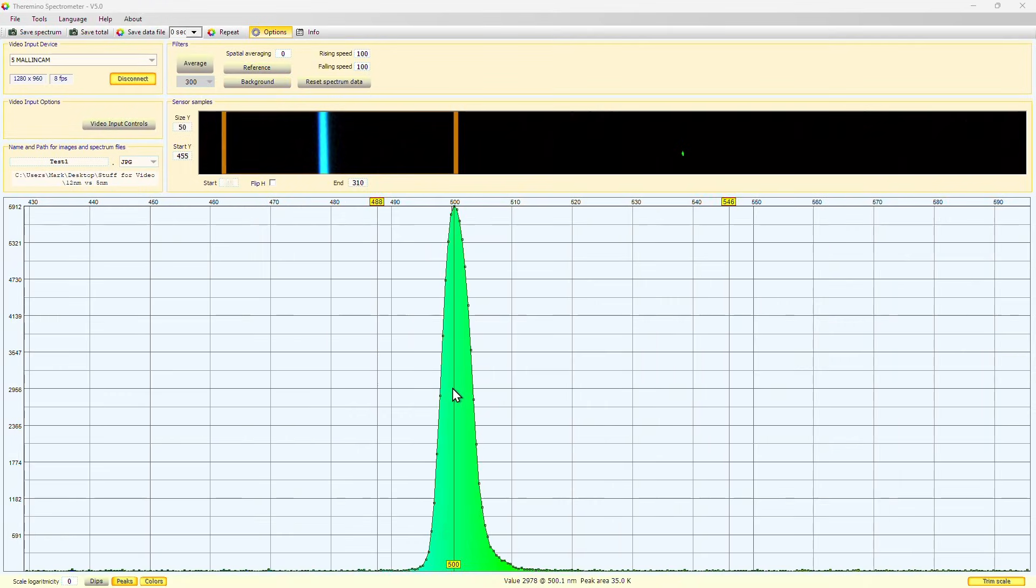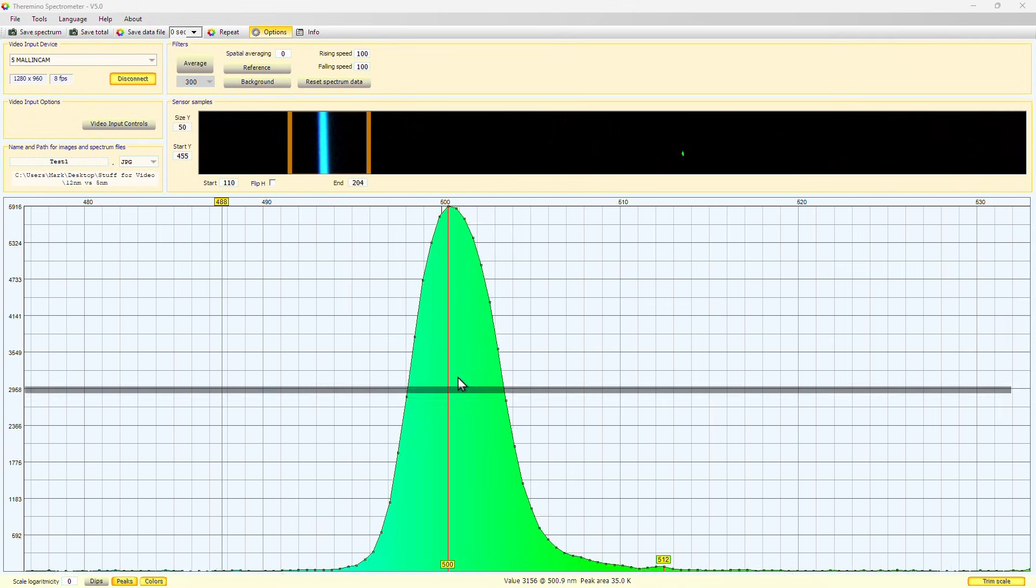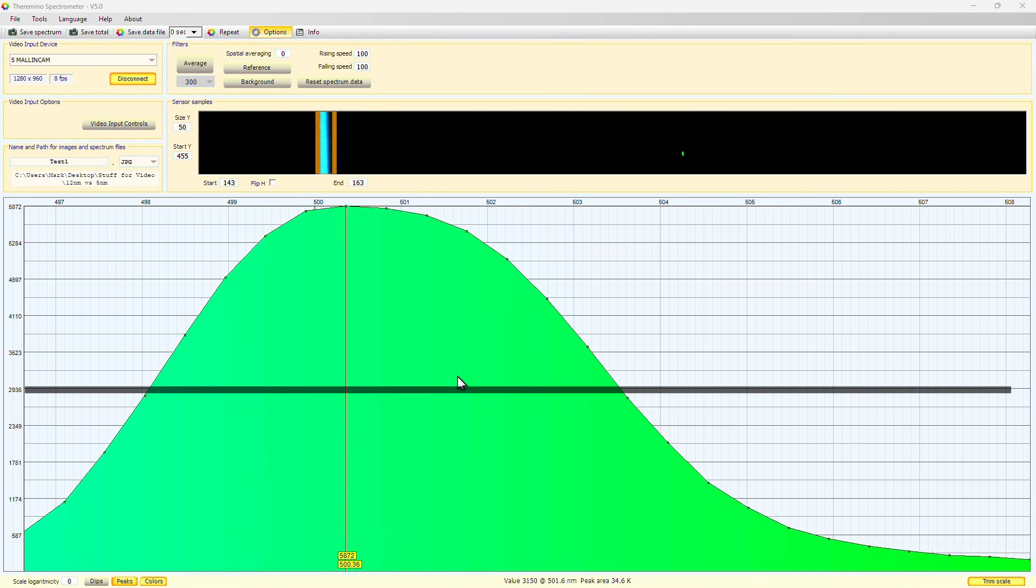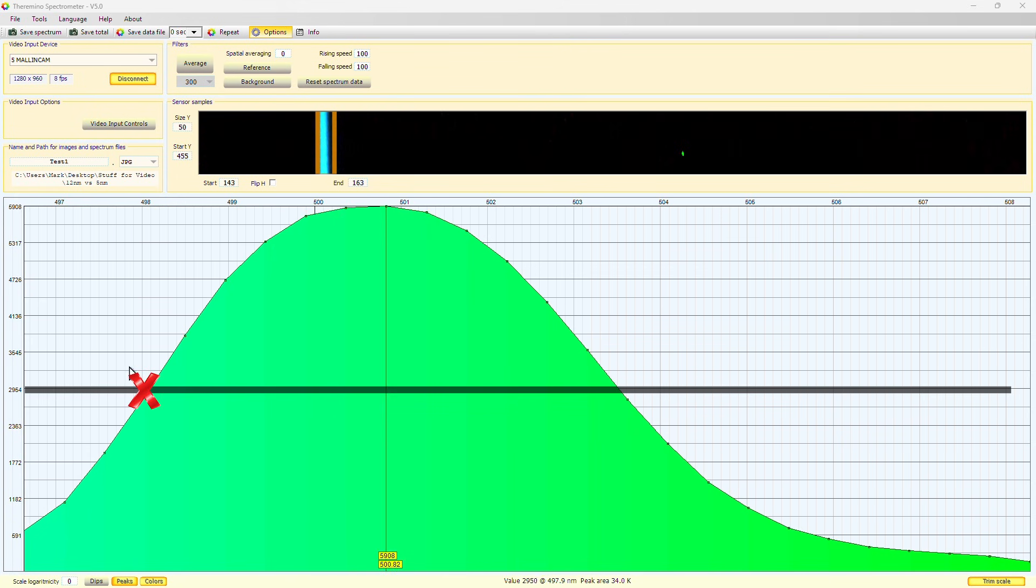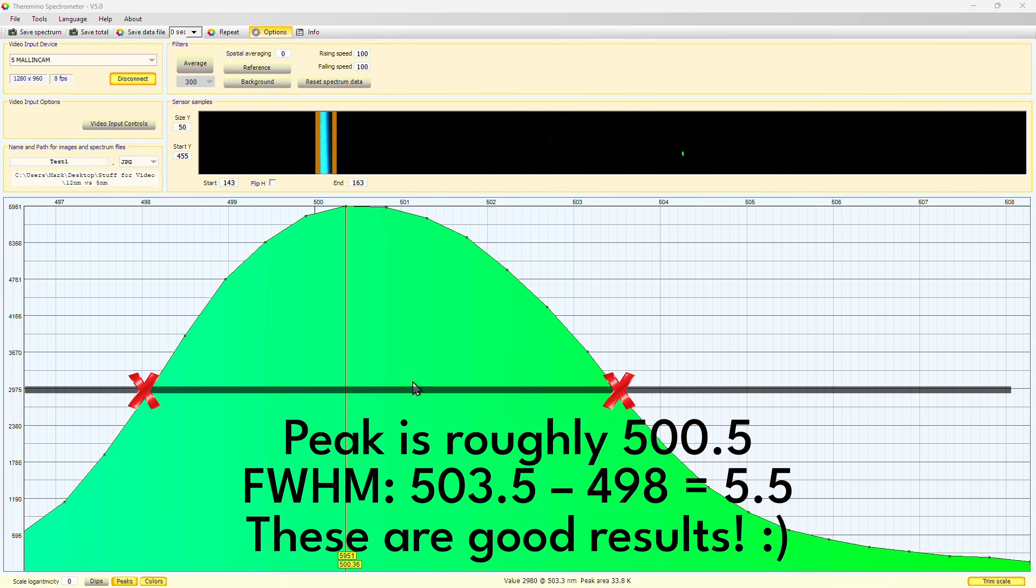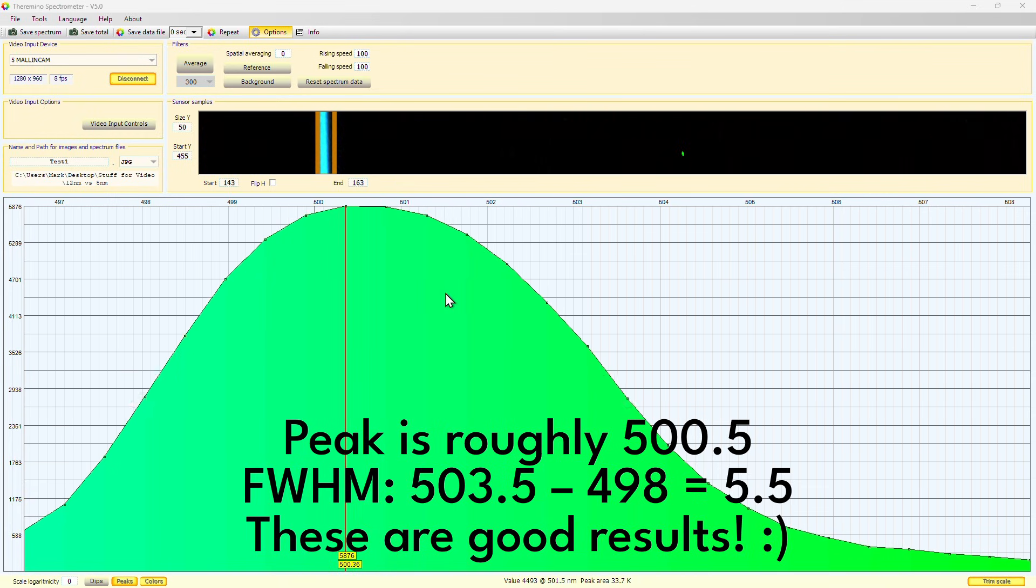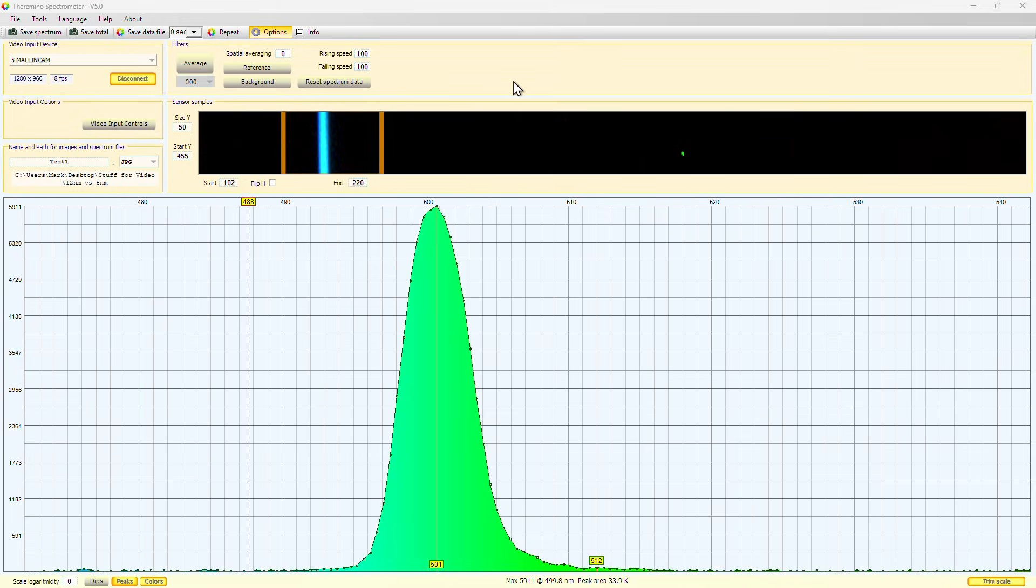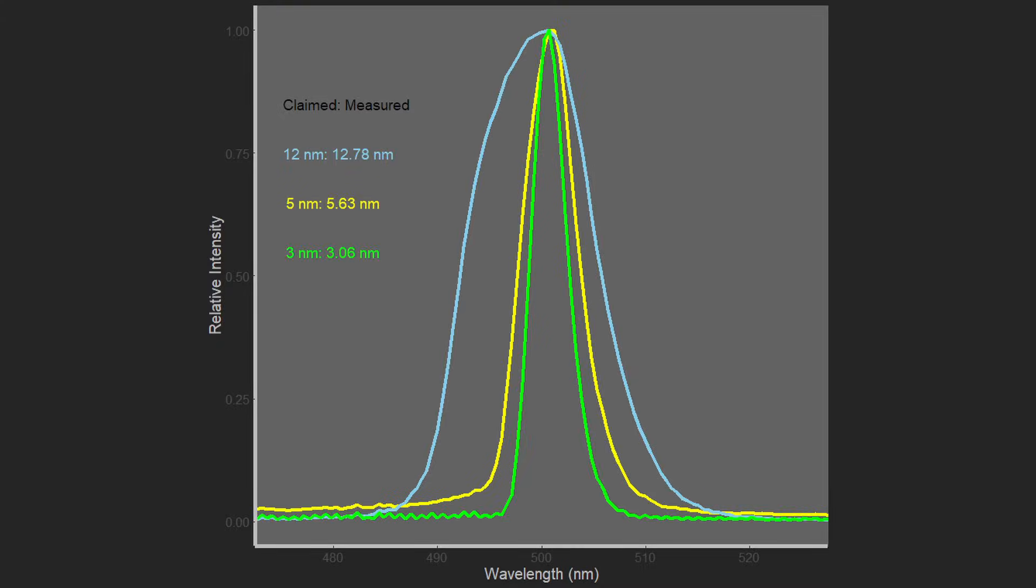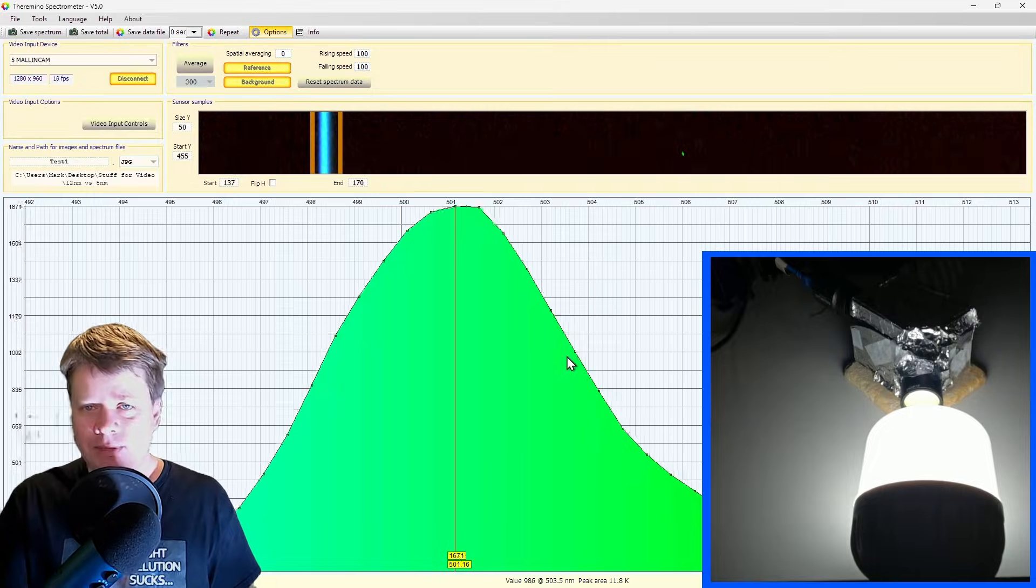But we can probably check the full width half maximum pretty well. So let's zoom in a second and about half of the intensity, at half of this peak, if we look at the y axis here is probably around 850. We can check and see that we're at 498 nanometers on the left side and 503, 504 on the right side. So that's a difference about 5.5. That's pretty good. I've tried this with other O3 filters and I've got similar results. So a 12 nanometer bandwidth O3 filter had a peak around 500 nanometers and a width of around 12 nanometers. I did the same thing with a three nanometer bandwidth filter and it gave similar results.